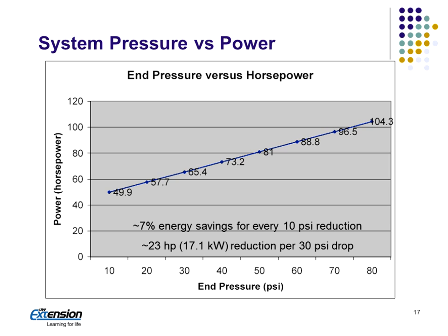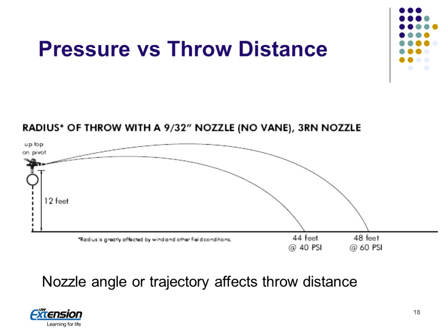So here's another example of looking at it. This is in horsepower. If we have a high pressure system, we'd need about 104 horsepower. This is for, I think, an 800 gallon per minute flow, and I think roughly a 100 foot pumping depth. We can get about 7% energy savings for every 10 psi. So if we were to come from 104 down to 81, we'd save 23 horsepower, or 17 kilowatts per hour of operation, with that 30 psi drop.